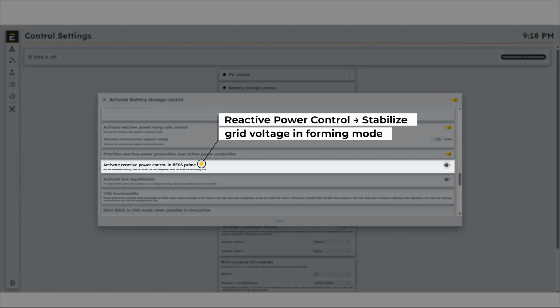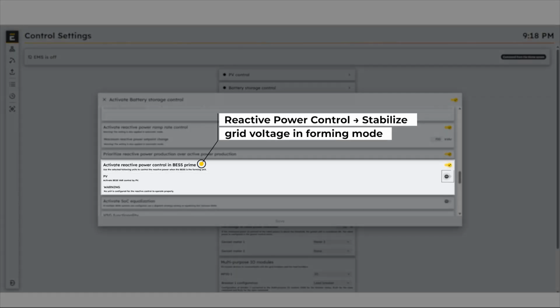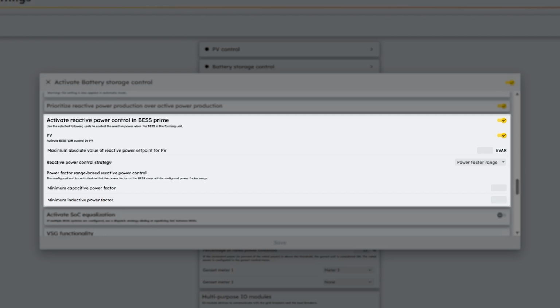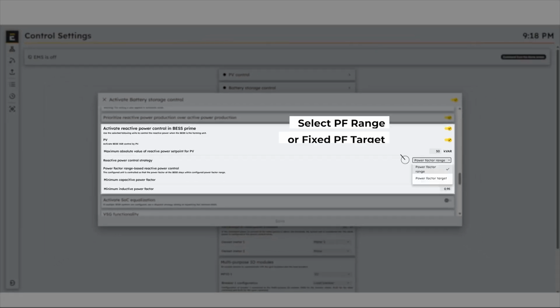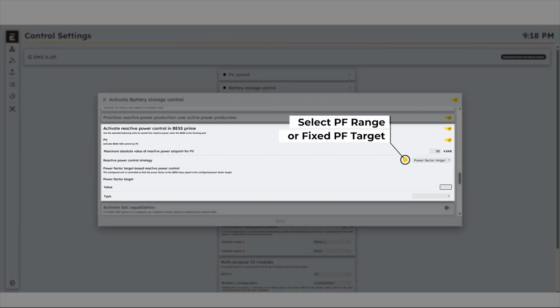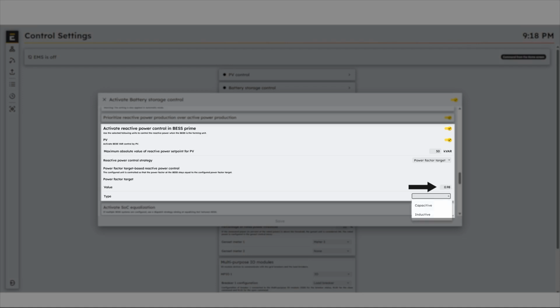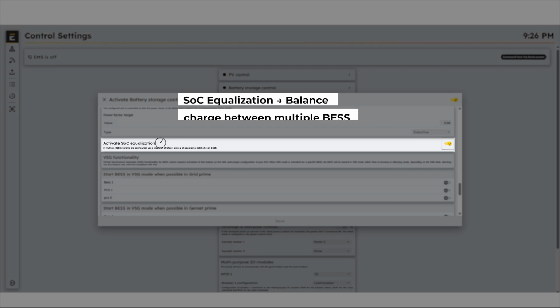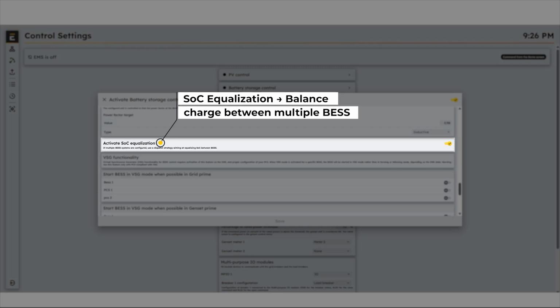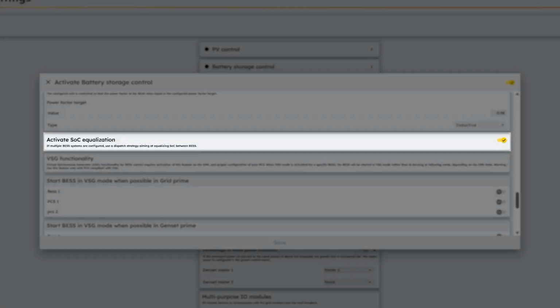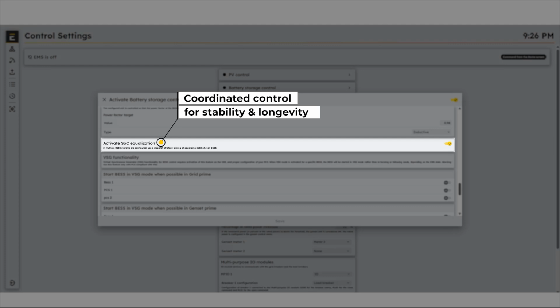When the BESS operates as a forming unit, the EMS can regulate reactive power to maintain voltage stability at the point of common coupling, mainly by adjusting the reactive power output of the PV inverters. You can choose between different control strategies, defined range, or dynamic target, depending on the site requirements. In multi-battery systems, SOC equalization ensures balanced operation by harmonizing the charge level of each BESS. This function is available only when the BESS operates as a following unit, allowing the EMS to optimize energy sharing between batteries.